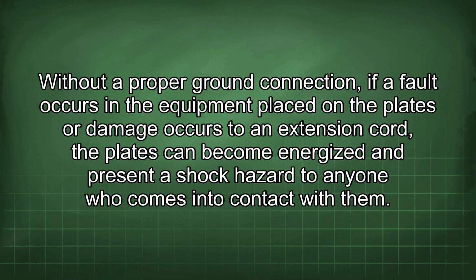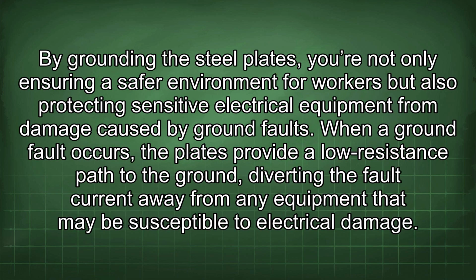Without a proper ground connection, if a fault occurs in the equipment placed on the plates or damage occurs to an extension cord, the plates can become energized and present a shock hazard to anyone who comes into contact with them. By grounding the steel plates, you are not only ensuring a safer environment for workers but also protecting sensitive electrical equipment from damage caused by ground faults. When a ground fault occurs, the plates provide a low resistance path to the ground, diverting the fault current away from any equipment that may be susceptible to electrical damage.